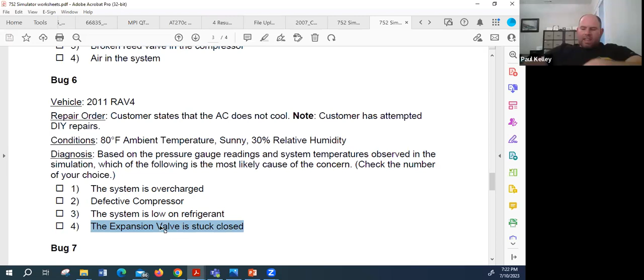Now, what would it look like if the TXV was stuck closed? Then it'd be almost vacuum on the low side and hella high on the high side, like that last one with 5 degrees on the temperatures — very low pressure and very cold.